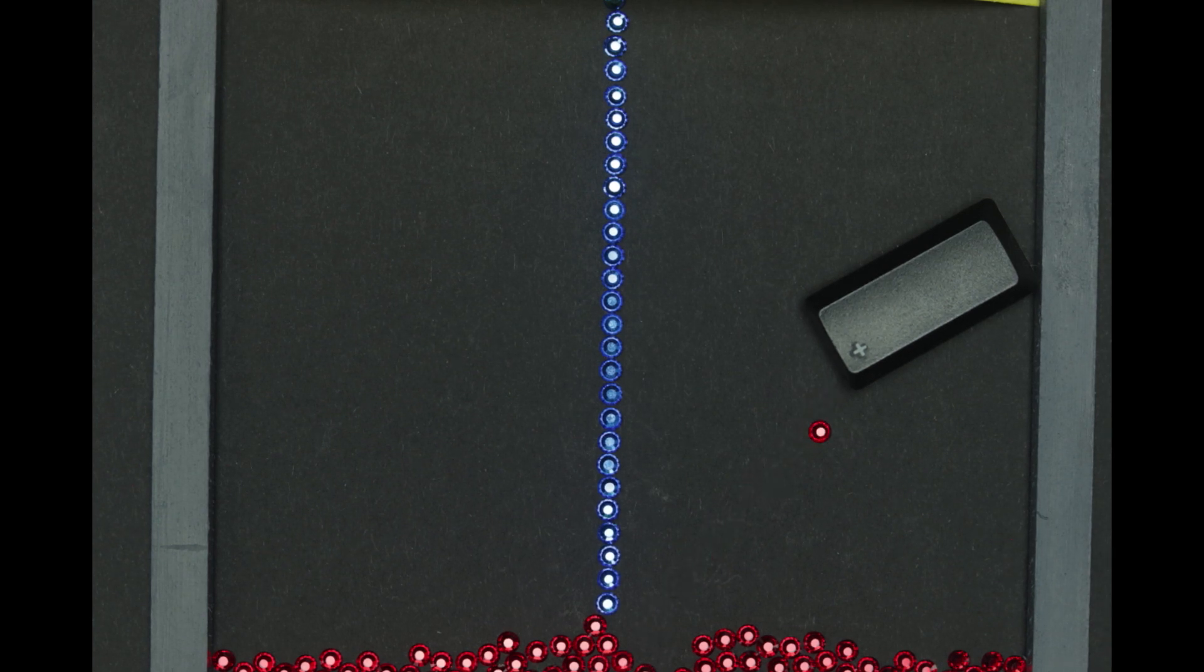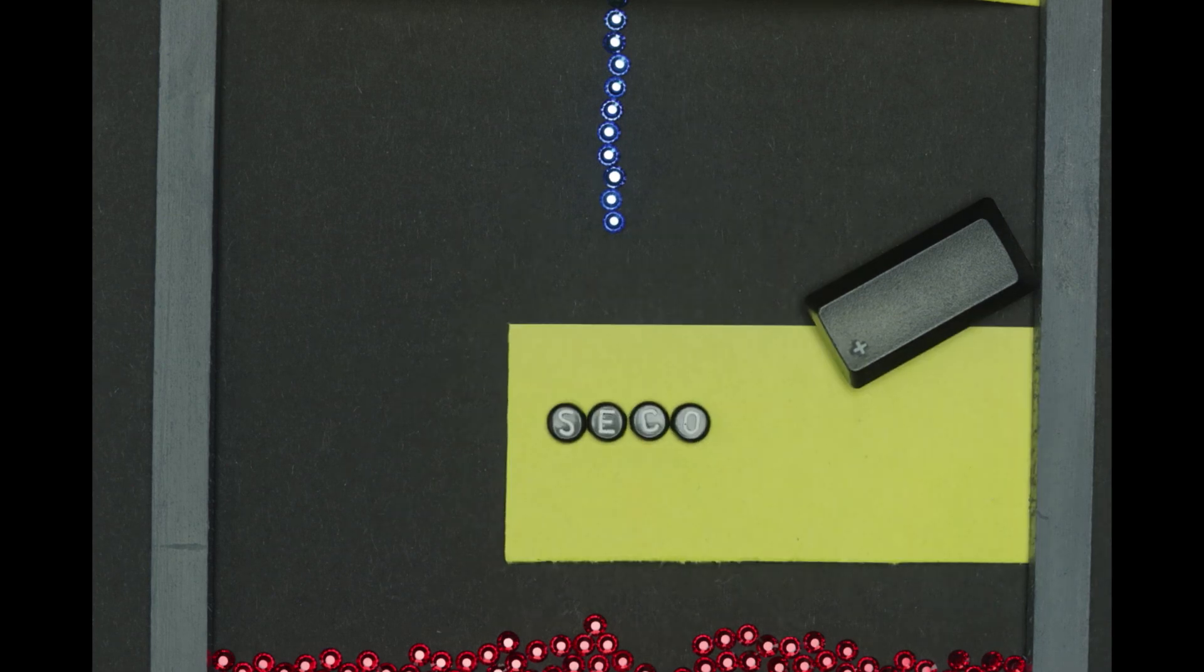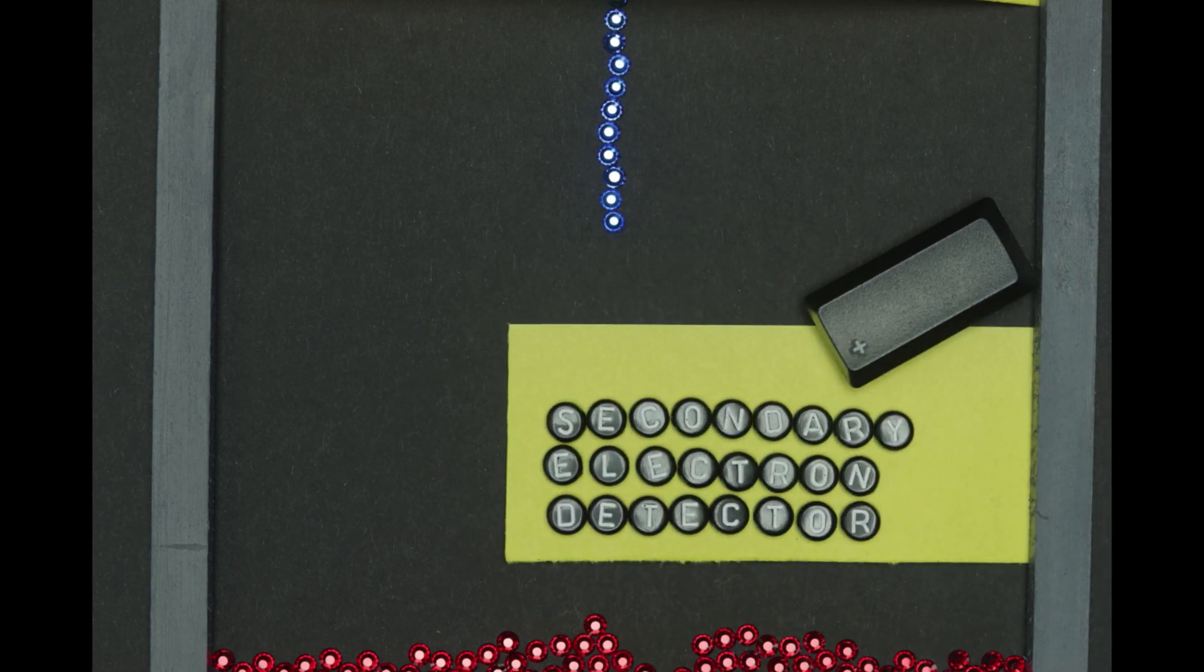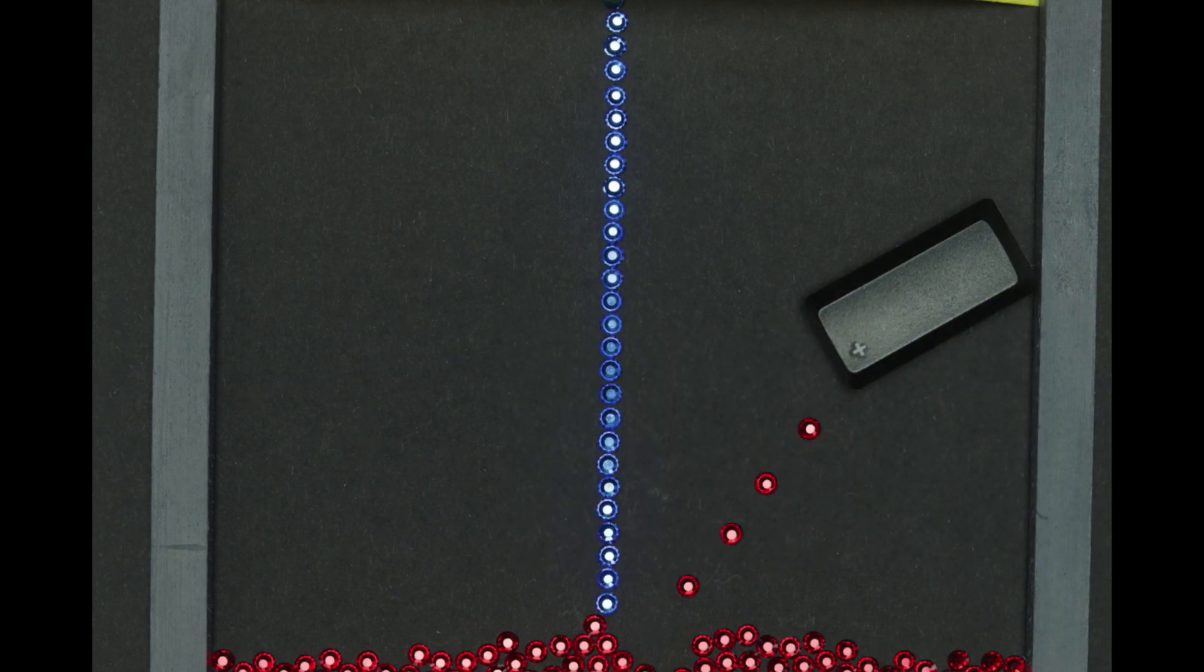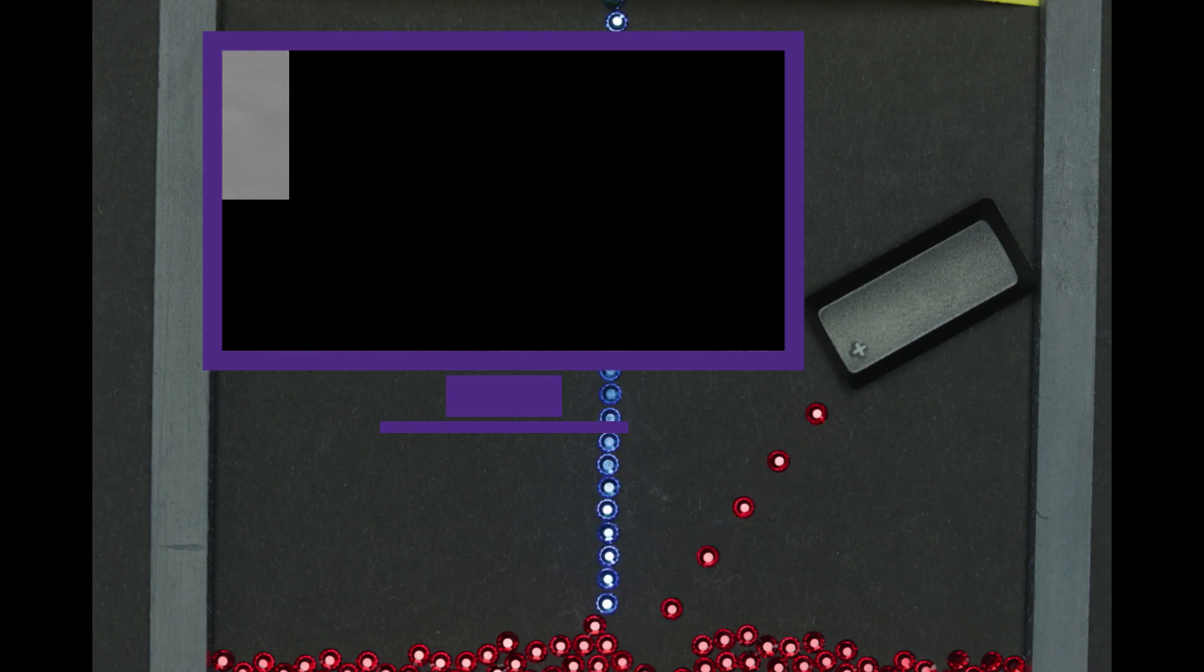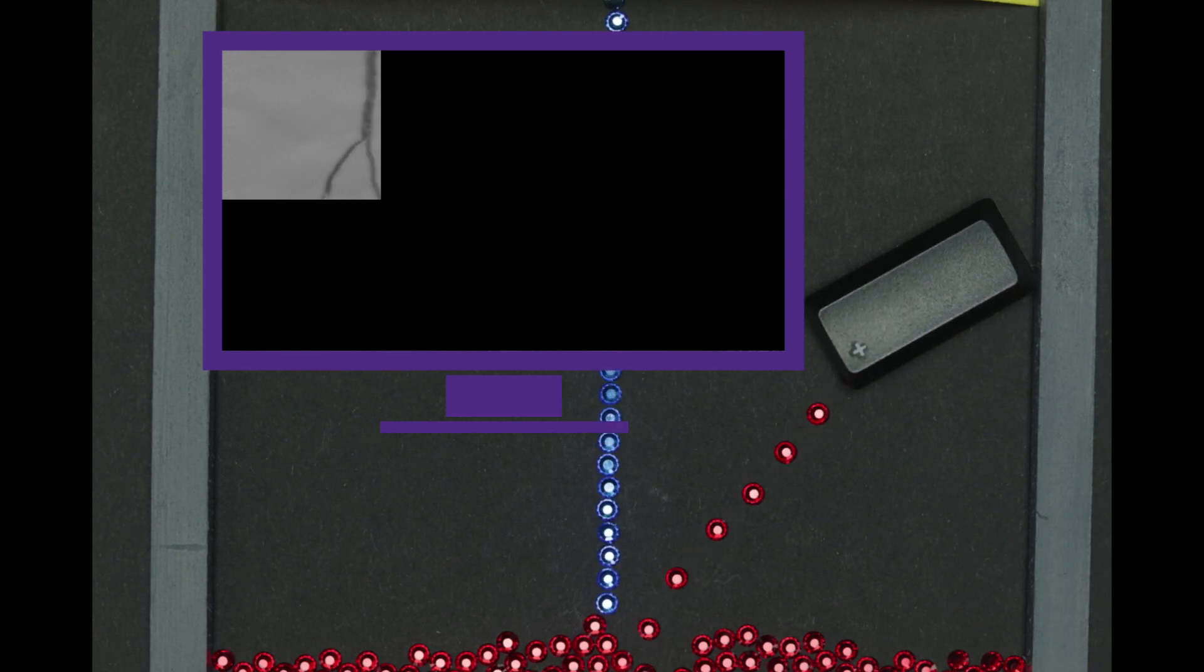The electrons that leave the sample are called secondary electrons. A special secondary electron detector inside the vacuum chamber has a positive charge which attracts the secondary electrons and transfers them into the computer. The computer produces the image one pixel at a time as it scans across the sample surface.